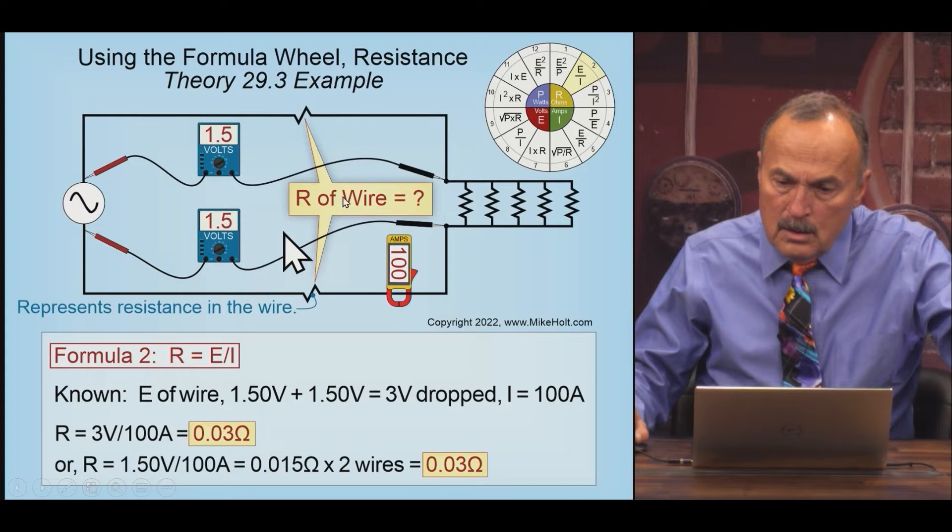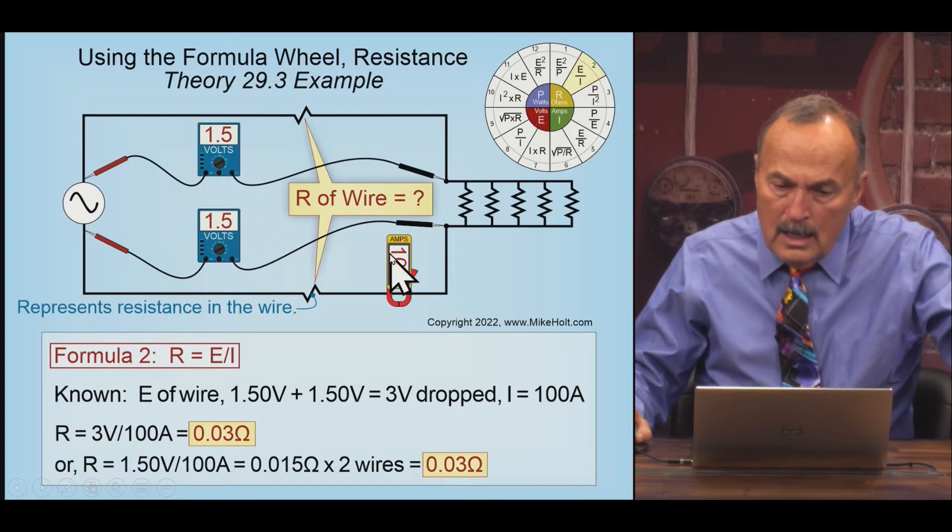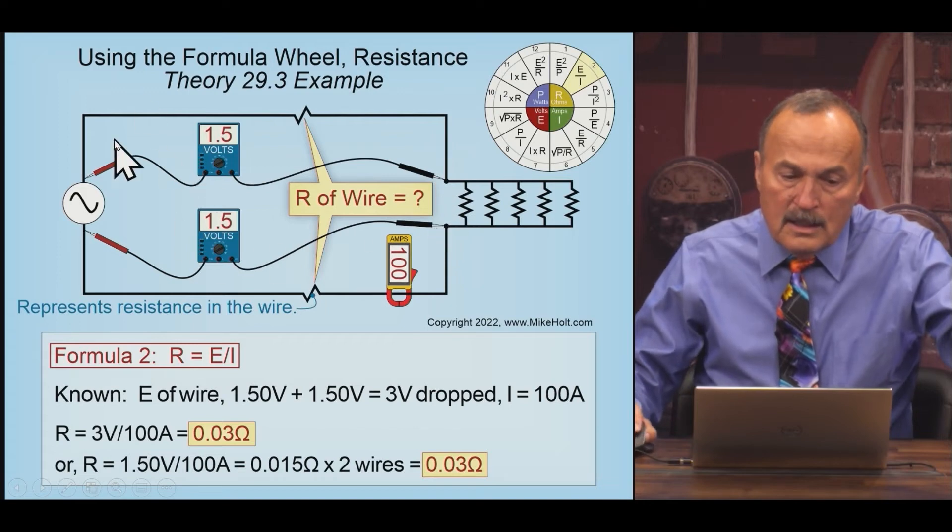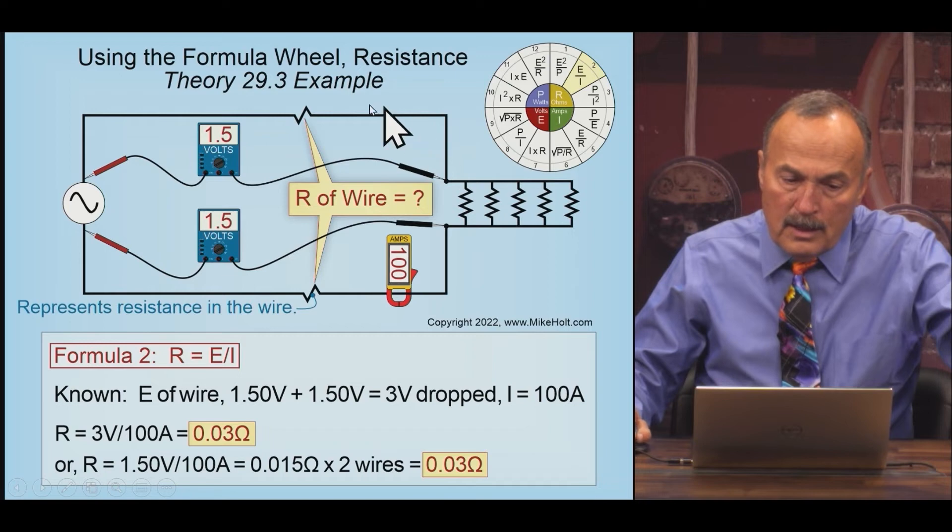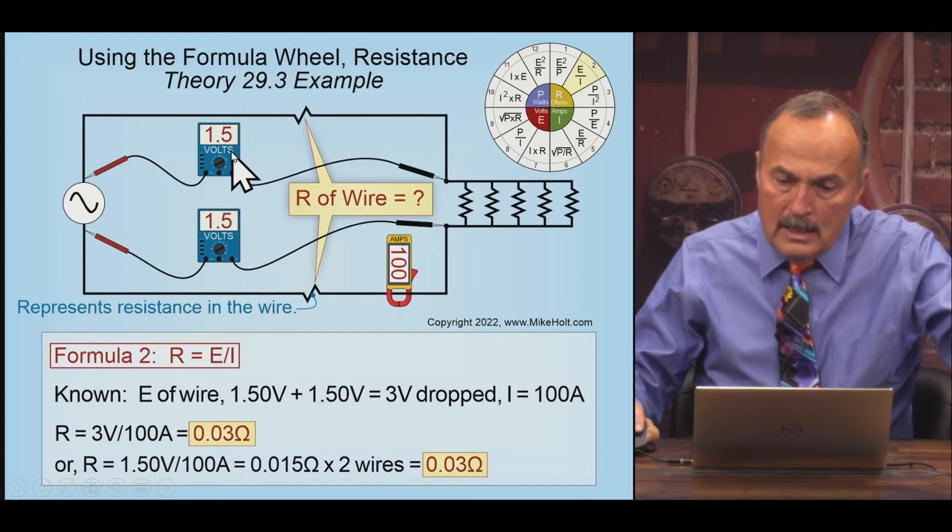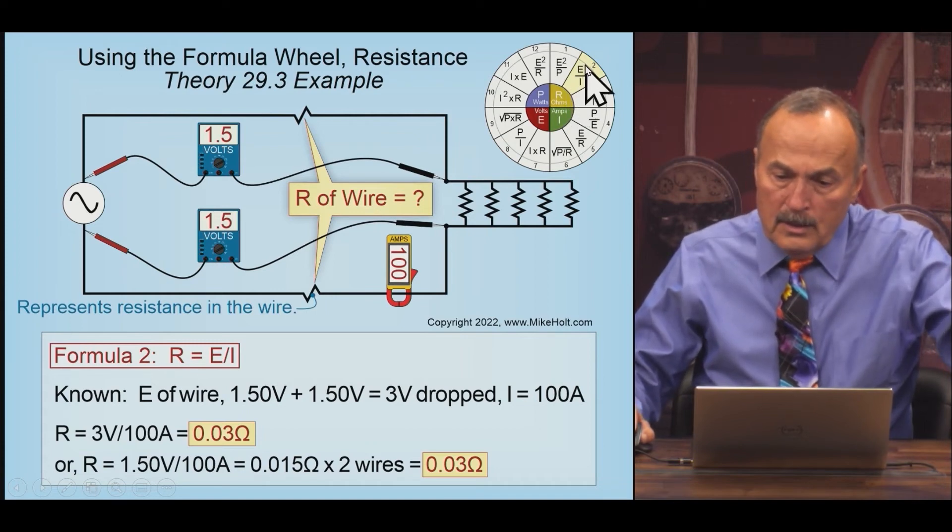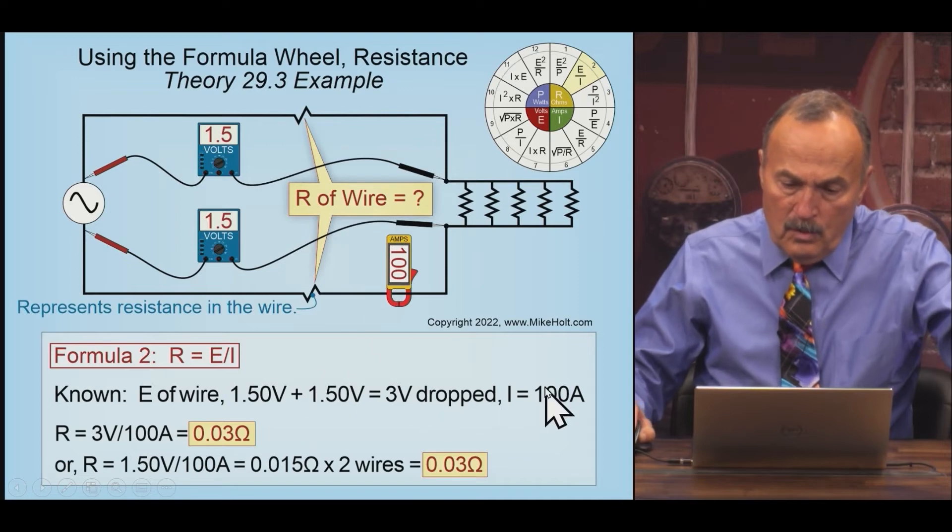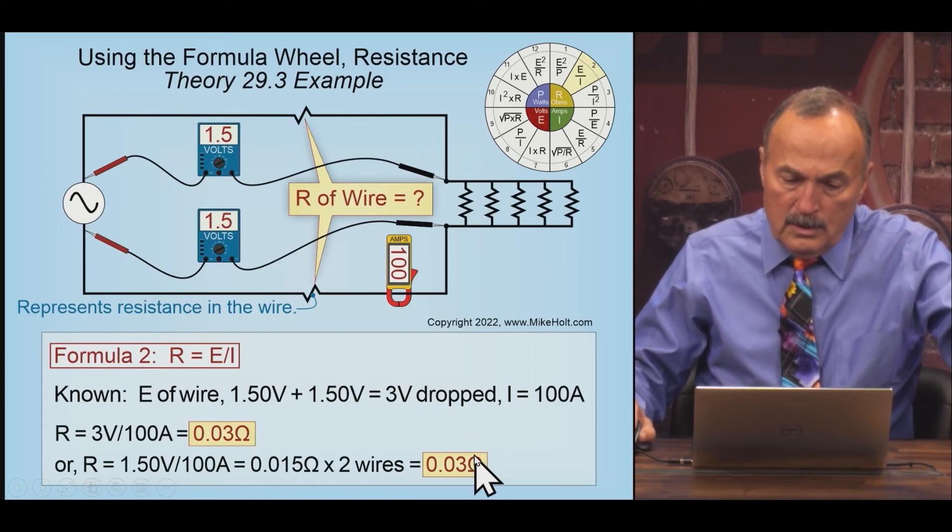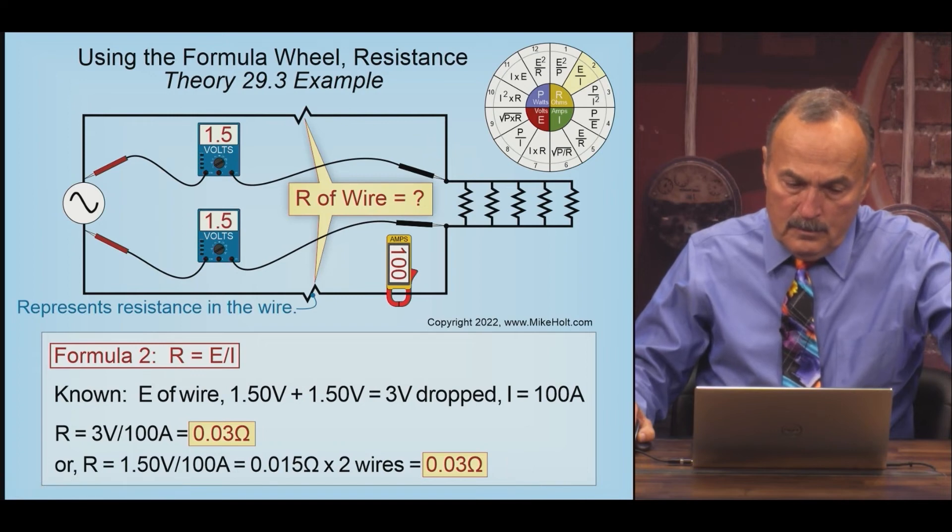I know I and I know E, the voltage. This is the voltage drop of the wire right here, from here to here. So I know I and E, and I'm looking for R. I and E is number two. That's going to be E over I: 3 volts over 100 amps is 0.03 ohms for the resistance of both wires. You can also do 0.015 ohms times two. Either way you get the same answer.